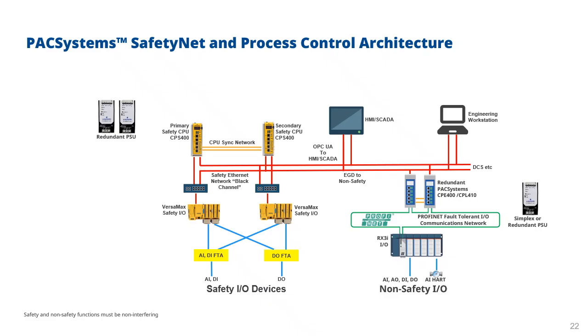A key point here, and on the previous slide, is your SafetyNet system and your process control system, they're all programmed using that same engineering workstation software, which is PAC Machine Edition. And because we've got OPC UA, you can integrate all of these into the same HMI SCADA solution as well, which of course for us would be Movicon.